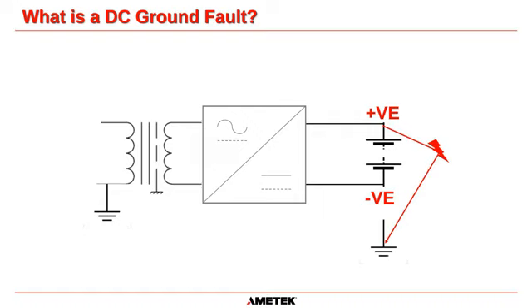So what is a DC ground fault? Well, a DC ground fault is when there is some form of connection between one of the poles of the DC. So in this circumstance, the positive of the battery has a path down to ground. That is the definition of a ground fault. Now, we don't know at this moment in time what the resistance of that fault is, but even if it's a high resistance, it is a connection between a pole and ground that is not supposed to be there. That's why it says a DC ground fault.